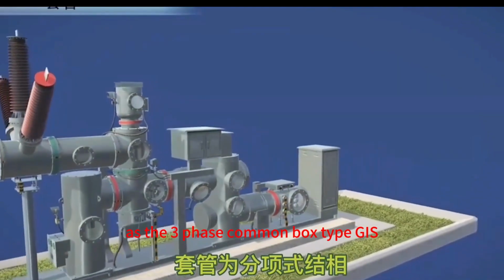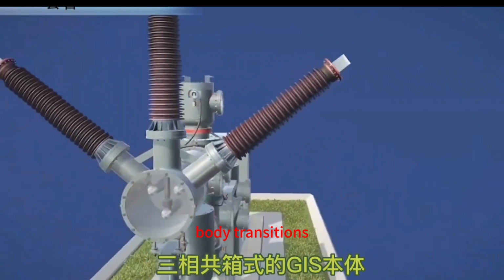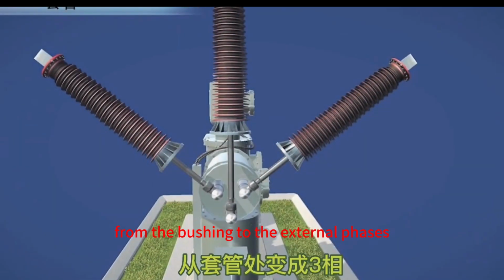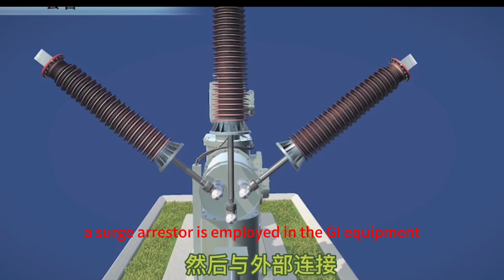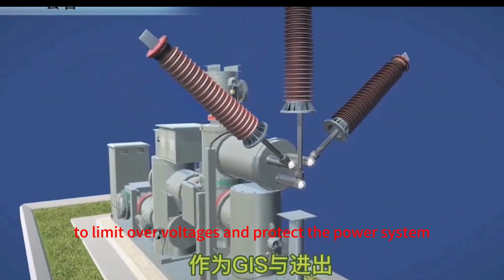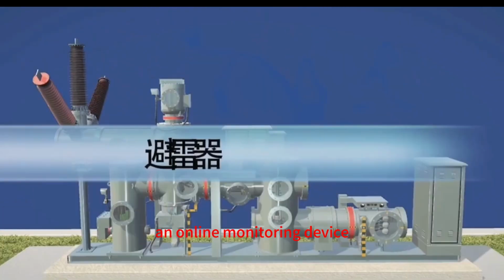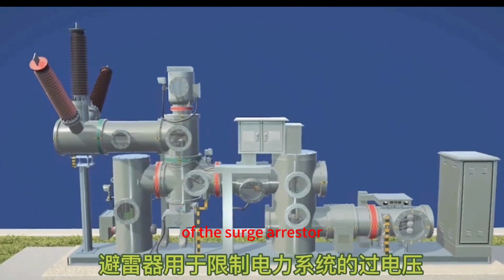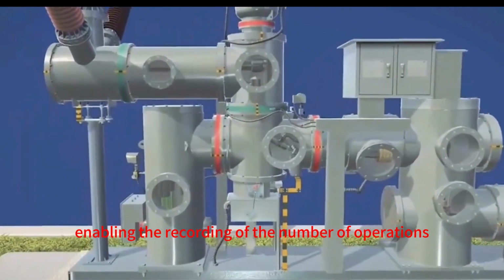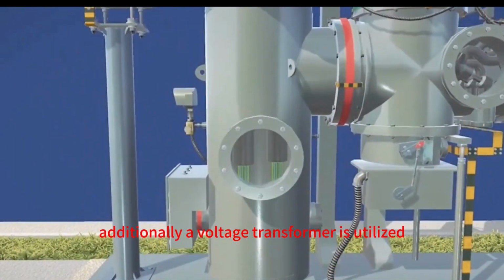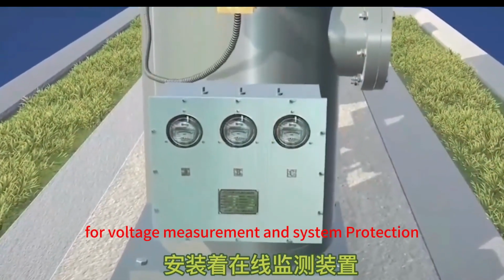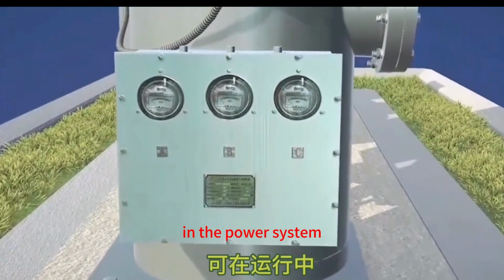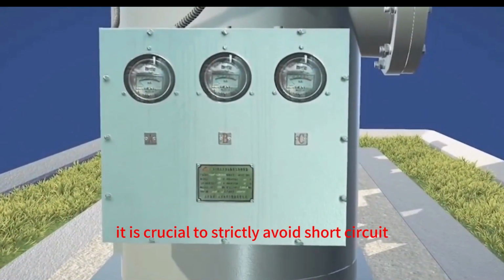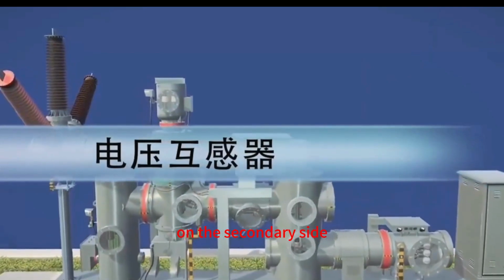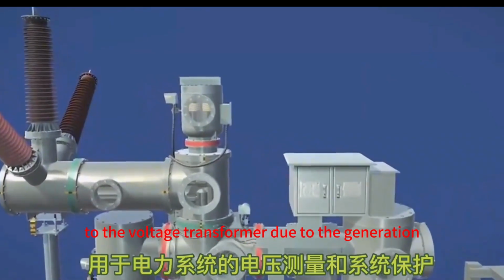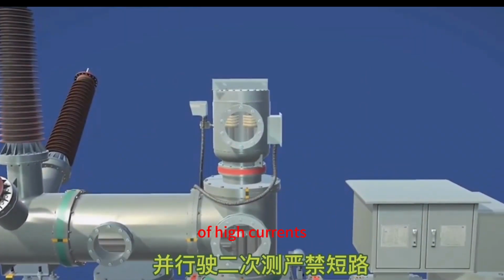As the three-phase common box type GIS body transitions from the bushing to the external phases, a surge arrester is employed in the GIS equipment to limit overvoltages and protect the power system. An online monitoring device is installed on the associated box of the surge arrester, enabling the recording of the number of operations and the current during operation. Additionally, a voltage transformer is utilized for voltage measurement and system protection in the power system. During operation, it is crucial to strictly avoid short-circuiting on the secondary side, as it may cause significant damage to the voltage transformer due to the generation of high currents.